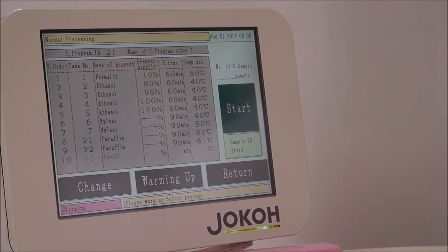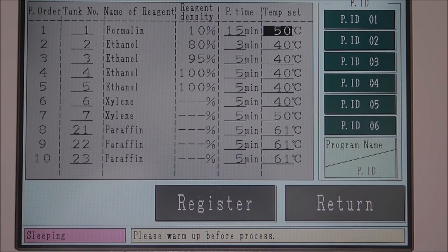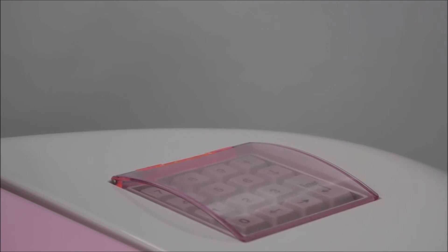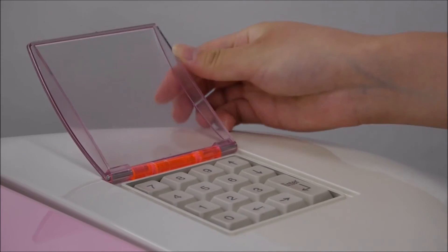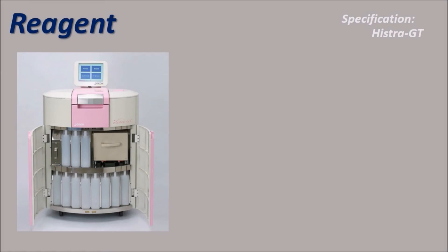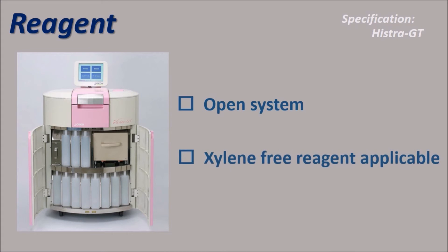This is how to set normal processing — very simple operation. If you want to change the temperature setting, enter manually by using the numerical keypad. JOKOH Histra-GT is an open system and works perfectly with any kinds of reagents, including xylene-free reagents.